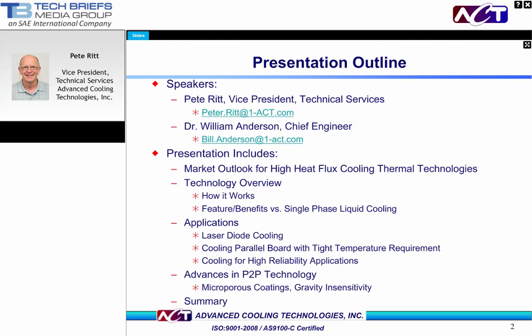Two-phase cooling generally means using a cooling fluid where at least some of the fluid is intentionally transformed into vapor upon heating, resulting in a vapor-liquid mixture in the fluid loop. Because a fluid's latent heat of vaporization can be 2 orders of magnitude larger than the sensible heat of single-phase liquid cooling, there can be a significant improvement in heat absorption per unit volume of fluid. Pump two-phase cooling has been the focus of research in government and academia, but is seeing more broad adoption in the commercial sector because of some very attractive performance features.